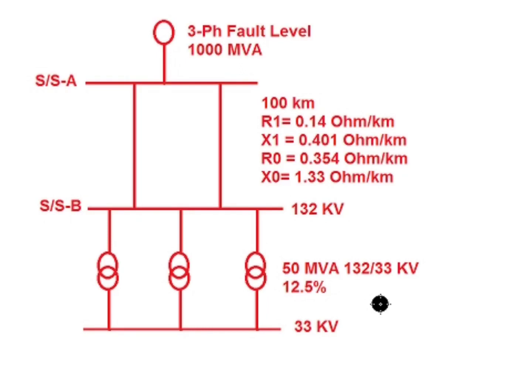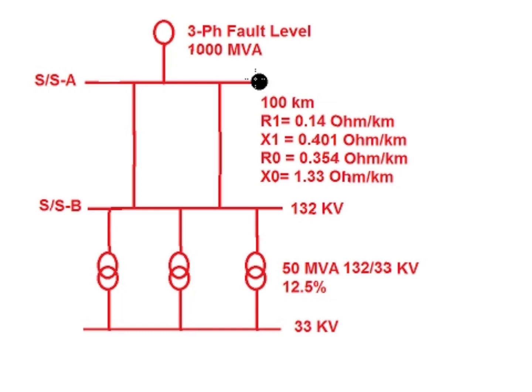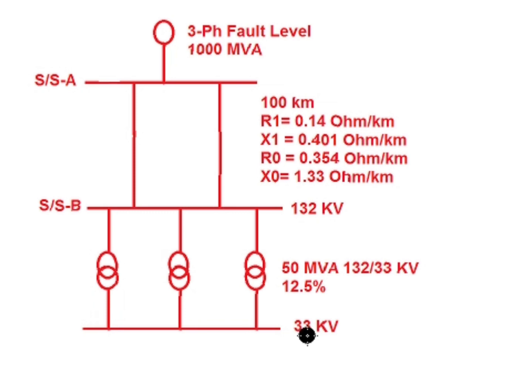Hello friends, today I will discuss about calculation of three-phase fault level for a particular substation. In this figure, substation A and substation B are connected via a double circuit line using a panther conductor. The line length is 100 km and substation A fault level is known — the three-phase fault level for substation A is 1000 MVA. In substation B there are three transformers, each 50 MVA, 132/33 kV, running under parallel condition. In this video I will discuss how to calculate the three-phase symmetrical fault at the 33 kV bus.